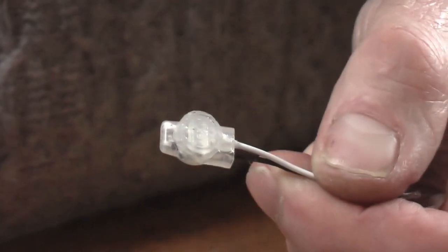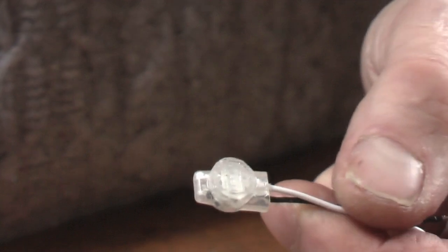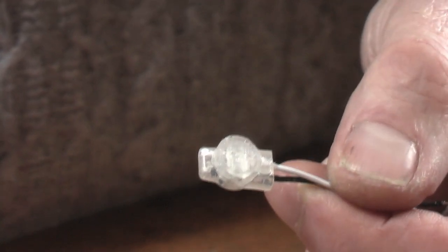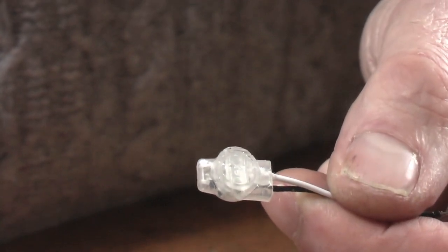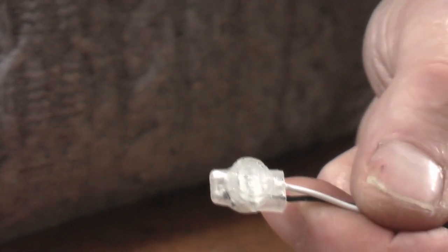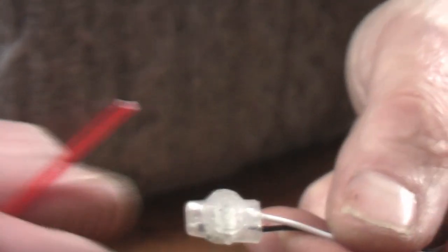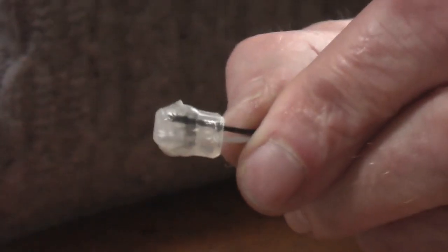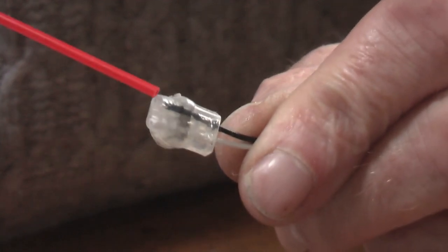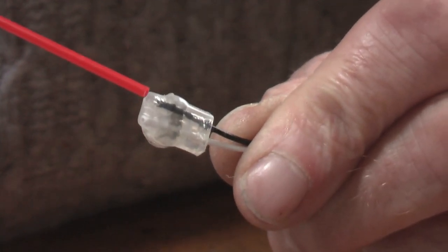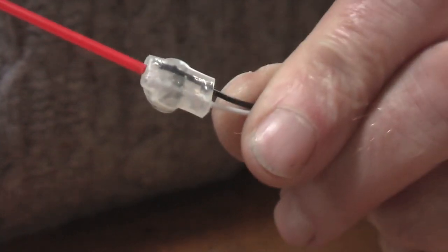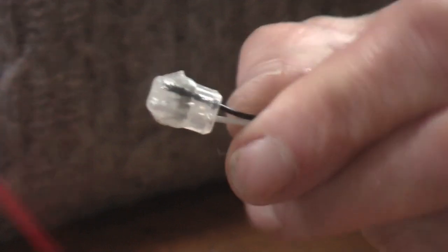The things you need to make sure of when using these: first, the wires must be unstripped before you insert them. Don't strip them, leave the insulation on. Then when you push the wires in, make sure you push them right to the very end of the connector. You can see inside the connector on the back that the wires are pushed right to the end, so that's important.